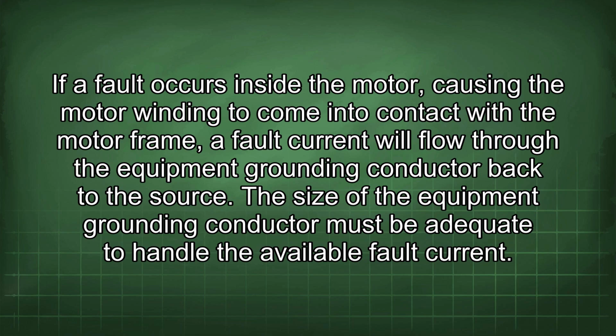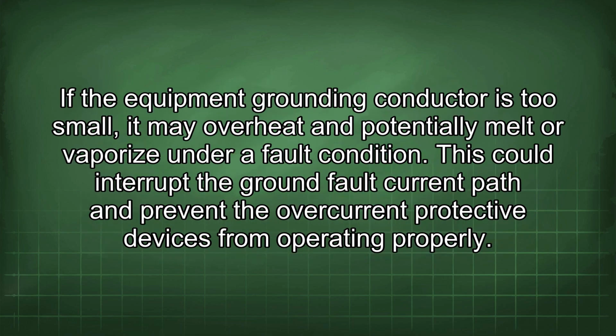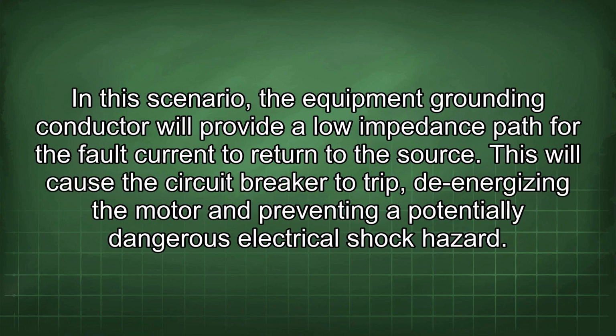If a fault occurs inside the motor, causing the motor winding to come into contact with the motor frame, a fault current will flow through the equipment grounding conductor back to the source. The size of the equipment grounding conductor must be adequate to handle the available fault current. If the equipment grounding conductor is too small, it may overheat and potentially melt or vaporize under a fault condition. This could interrupt the ground fault current path and prevent the overcurrent protective devices from operating properly. In this scenario, the equipment grounding conductor will provide a low impedance path for the fault current to return to the source. This will cause the circuit breaker to trip, de-energizing the motor and preventing a potentially dangerous electrical shock hazard.